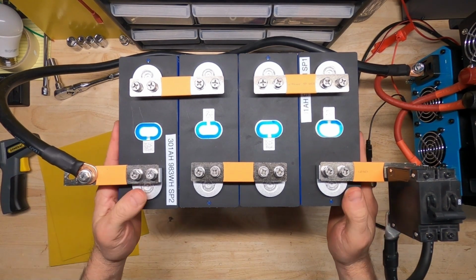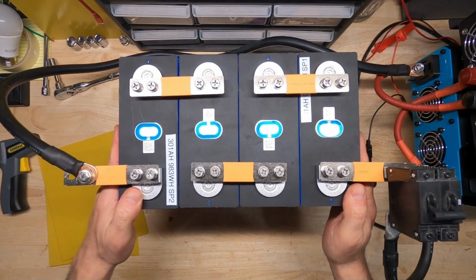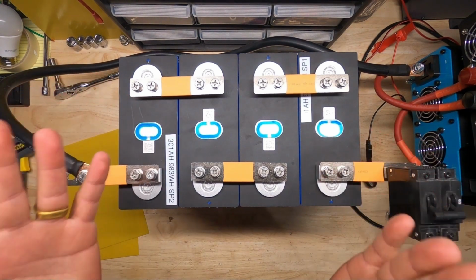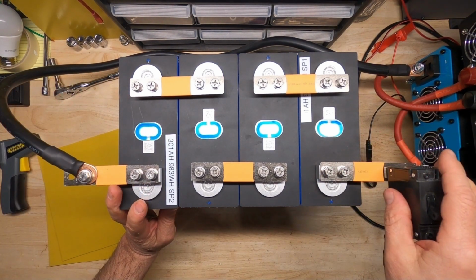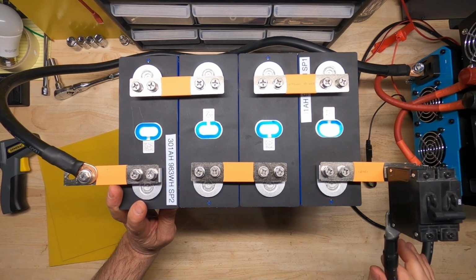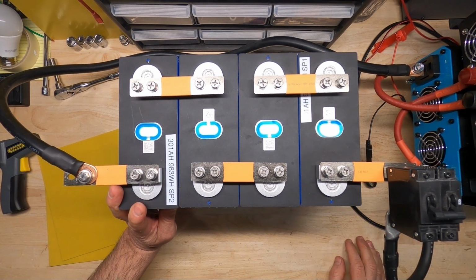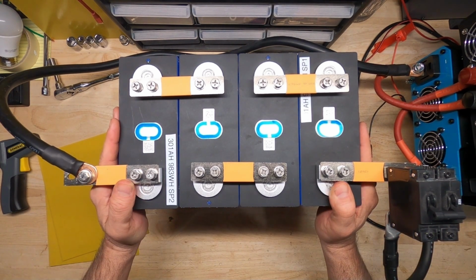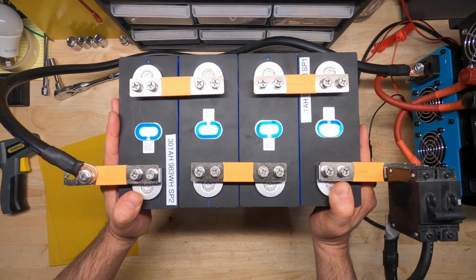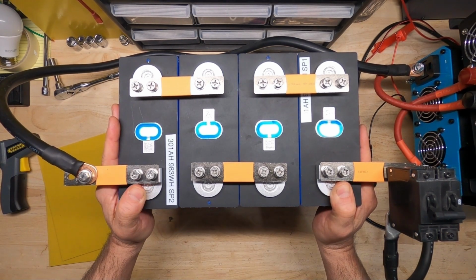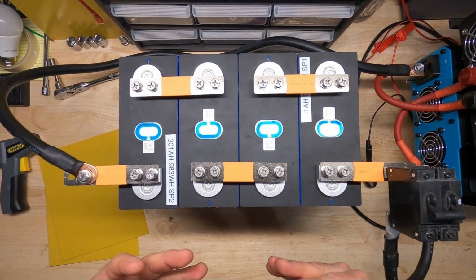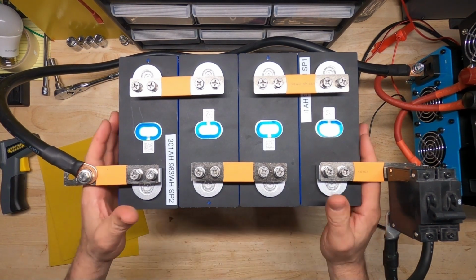We have these wired without a BMS. We're just going to run it raw, because all we need to do is produce enough current to be able to heat up this breaker and trip the breaker and heat up this cable and see how hot it gets. So the max we'll probably run the test for is about 10 minutes. That should be enough. We'll just monitor the heat. If it does not continue to get hotter, then this test will be done.